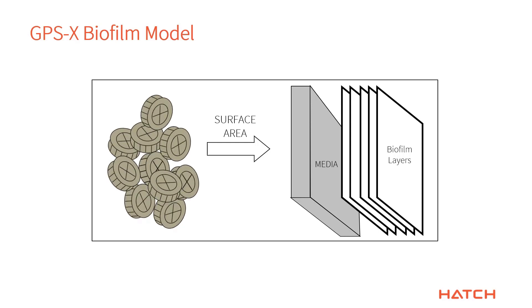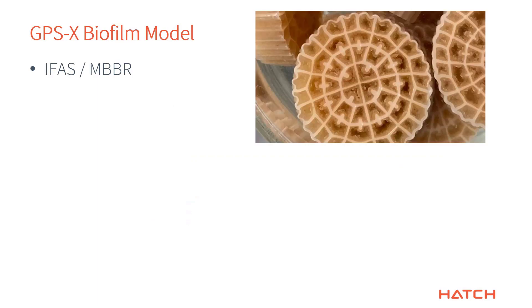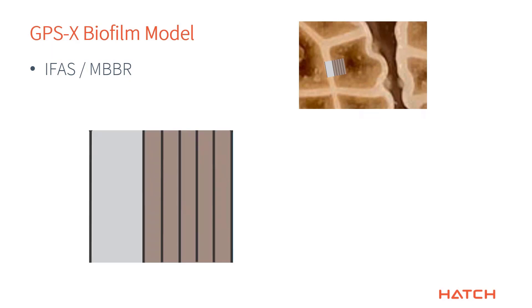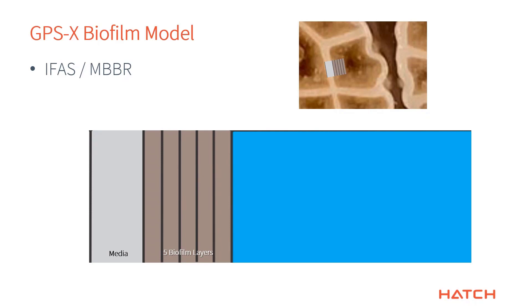In an IFAS/MBBR model, that outer biofilm layer is in contact with all the rest of the liquid, which is assumed to be completely mixed outside that reactor. So basically you have five biofilm layers and then the bulk liquid layer. I tried to give a physical representation of this: taking a tiny slice of the plastic media, you can see those five biofilm layers standing on it. This is an average representation — we know layers vary in thickness — but it's the standard way of modeling these systems.